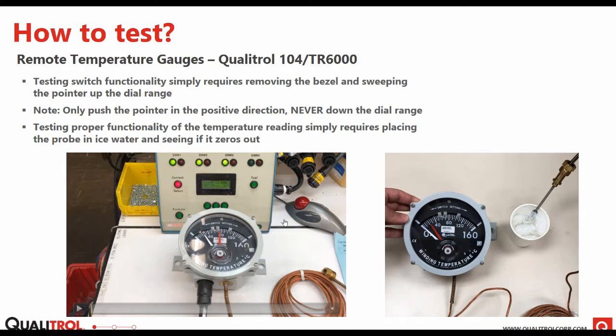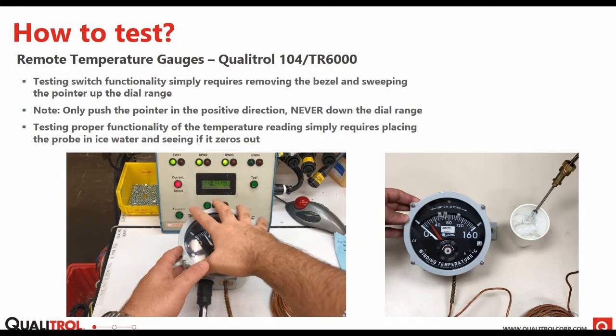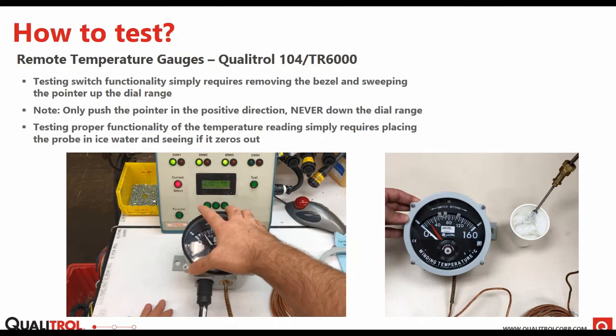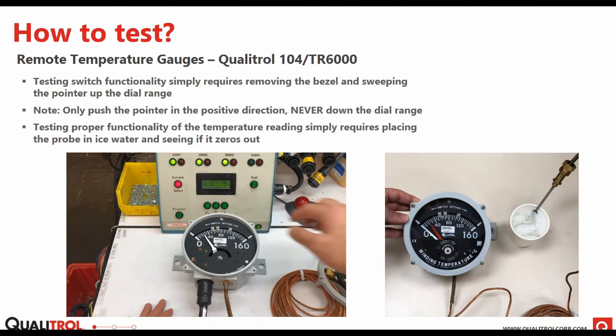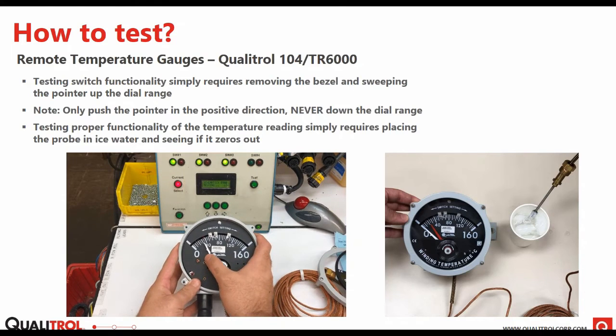So this here on the left is our 104 and TR6000 family. It's also nearly as simple, if not simpler, than the liquid level gauge. All it requires is to remove the front bezel, remove the front lens, and then you can actually push the pointer up the dial to actuate each switch. And this won't cause any harm to the gauge at all, as long as you don't push it down from where the temperature range is currently sitting. So right in this video, we're at about 25 C.